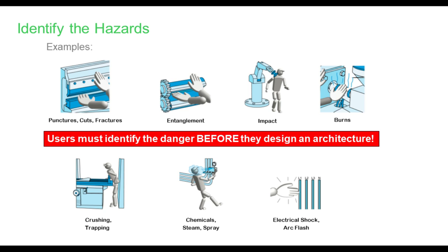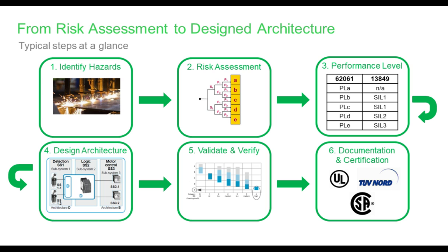In the industry, they use the term task-based risk assessment, and this is really what we need to do. What are the tasks, what are the jobs that need to be done, and what are the hazards associated with them? That's when you do your risk assessment. Based on that, you can design the right equipment to protect people from hazards. There are multiple standards that have different specific ways of doing risk assessment. And there is no law, and even OSHA does not specify exactly which methodology we need to use. But we really do need to be using some kind of methodology.